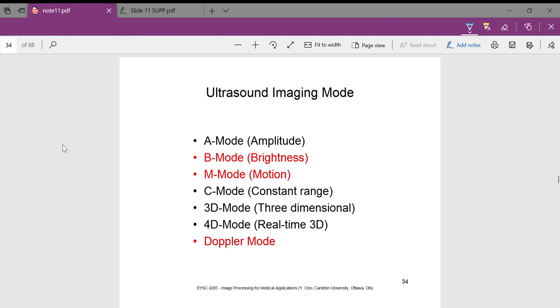There are different types of ultrasound imaging known as different modes. The starting point is the envelope-detected signal called the A-mode signal or amplitude mode signal. By firing the transducer on a repetitive basis, a succession of these signals can be displayed on an oscilloscope — this is the A-mode scan. B-mode image comprises a series of bright dots and uses the intensity of the reflected echoes to determine the brightness of the dots. M-mode scan is obtained by using each A-mode signal as a column in an image, where the value of the A-mode signal becomes the brightness of the M-mode image.